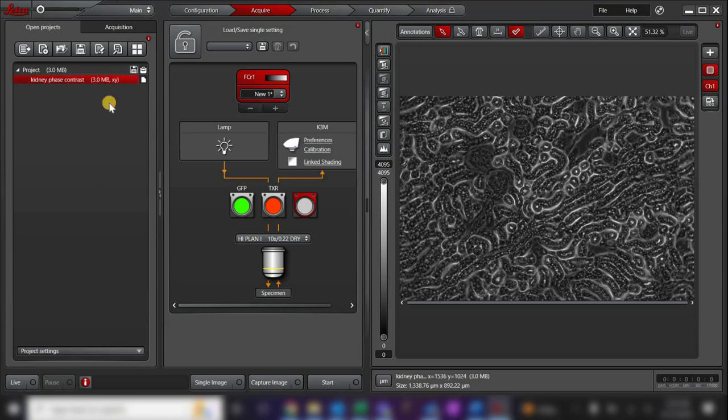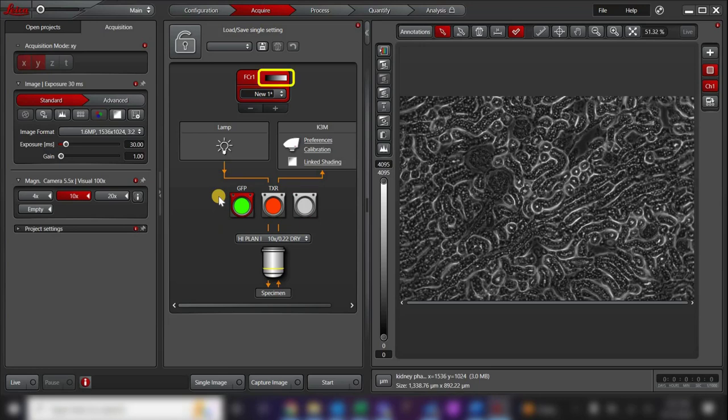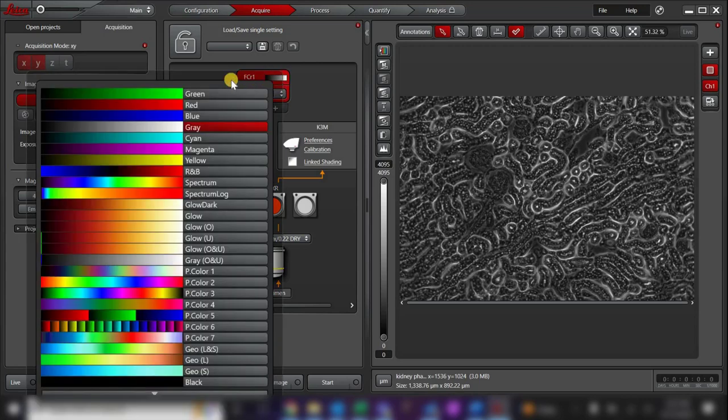Now let's go over how to take an image in fluorescence. Taking a fluorescence image is similar to taking a transmitted light image with a few small differences. First, let's navigate away from the Projects tab and back to the Acquisition tab. Select the filter cube you wish to use, then manually move the correct filter cube into place. For fluorescent images, many people choose to use a lookup table to color their images. Double-click on the color bar while you are not in live mode and select the color you wish to use. In this case, I'm taking an image of GFP labeling in my sample, so I'll choose a green lookup table, but you can choose any color you wish from the list.